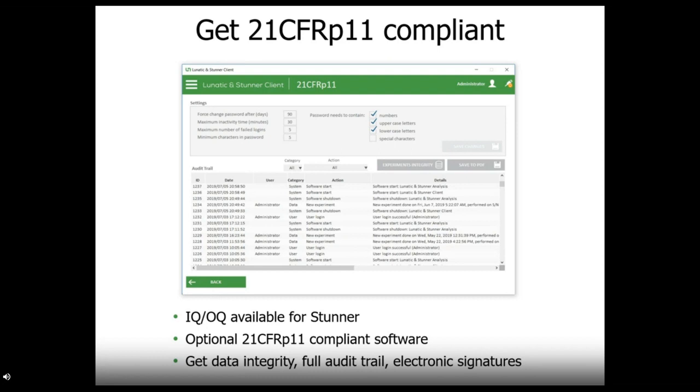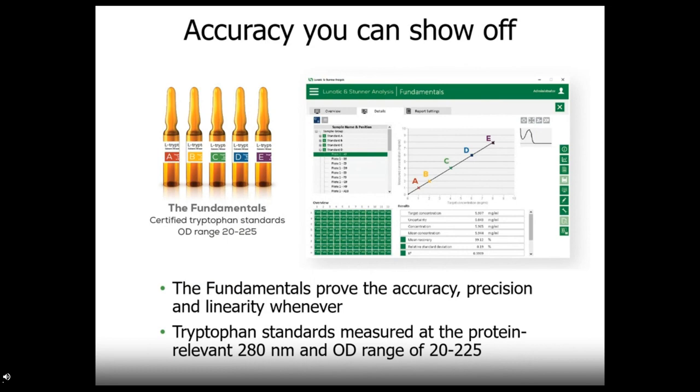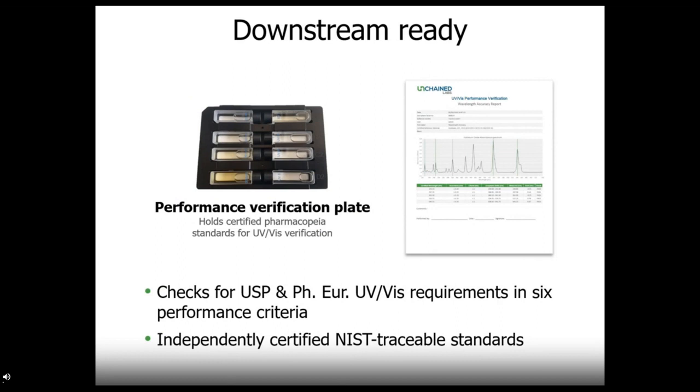We offer IQ OQ services and Stunner software is 21 CFR Part 11 compliant with full audit trail and electronic signature capabilities to help you achieve full integrity on your experiments and reports. And Stunner has shocking accuracy and wants to prove it. Using the fundamental tryptophan standards, the accuracy, precision, and linearity of the instrument can be proven at any time. At the protein-relevant 280 nanometer wavelength, OD ranges from 20 to 225. Be confident about every sample with data that leaves no room for doubt. And the features don't stop there. If you would like to move Stunner downstream, we also have a performance certification. These tests with certified cuvettes meet the United States Pharmacopeia and European Pharmacopeia guidelines for UV-Vis spectrometers. The tests and all necessary calculations are handled automatically by the software.